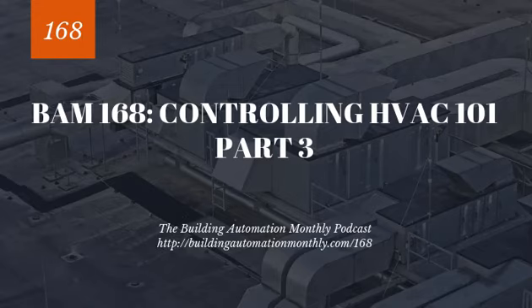So just to recap, you take the delta of the return versus supply temperature, times 8.33, times the gallons per hour. That gives you your BTUs per hour. Divide that by 12,000, and then times it by 1.2, and that should give you your tonnage for your central plant.